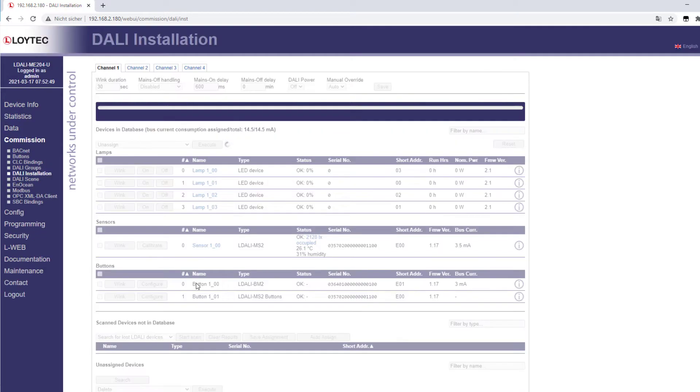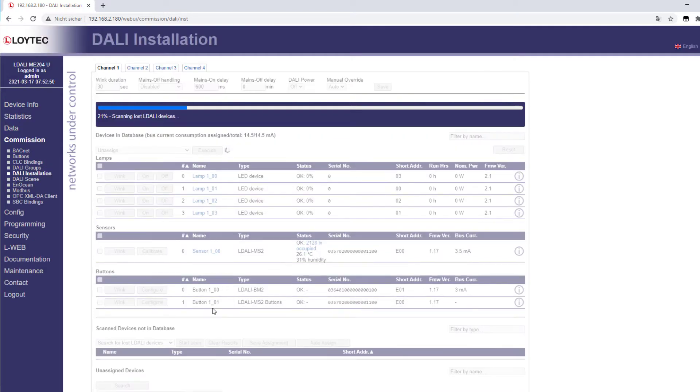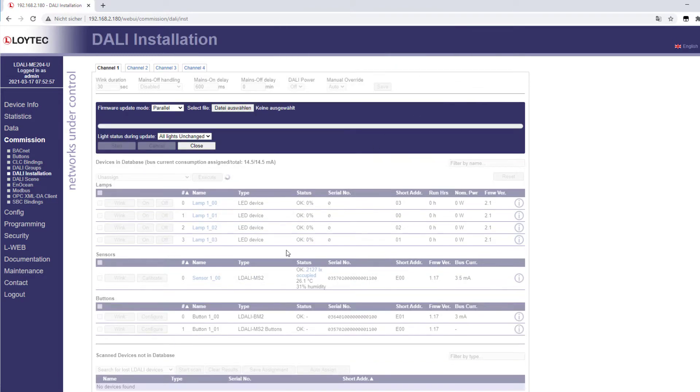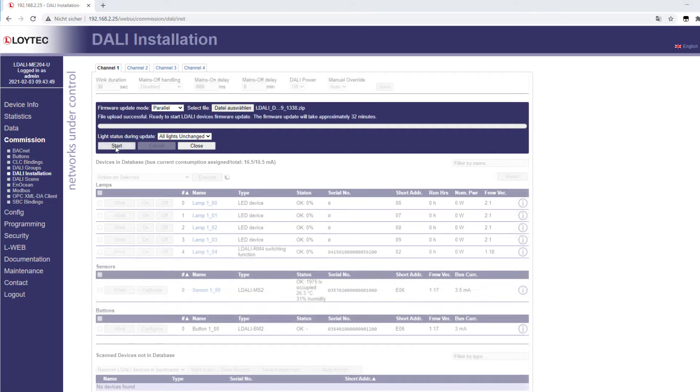Restoring L-DALI devices in the bootloader is a tool that can be used to restore devices that are stuck in the bootloader, for example due to a power failure during the firmware update. This function only searches for L-DALI devices in this state. If such a device has been found, the new firmware must now be imported.